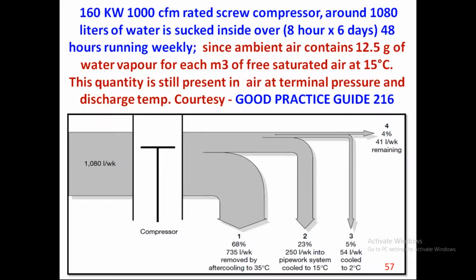Then comes the receiver and the pipe work, and what is the water ingress. Then comes the refrigerant dryer. So the water has to be removed in stages: one from the post air cooler, then from the receiver, then from the dryers, and from all the filters also.